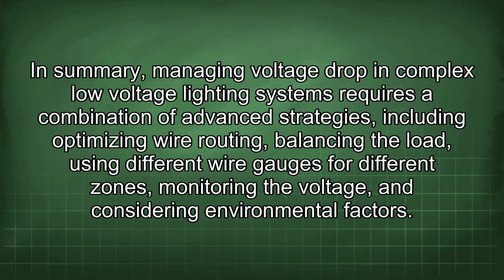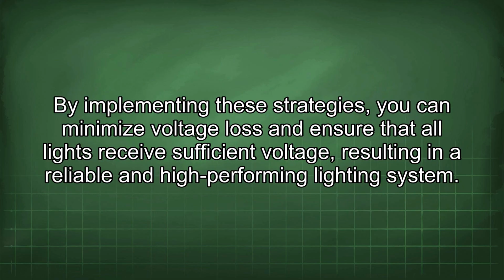In summary, managing voltage drop in complex low-voltage lighting systems requires a combination of advanced strategies, including optimizing wire routing, balancing the load, using different wire gauges for different zones, monitoring the voltage, and considering environmental factors. By implementing these strategies, you can minimize voltage loss and ensure that all lights receive sufficient voltage, resulting in a reliable and high-performing lighting system.